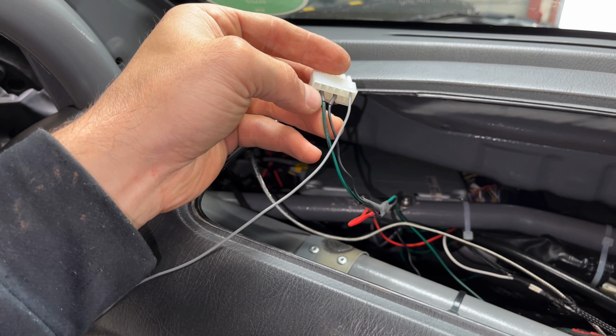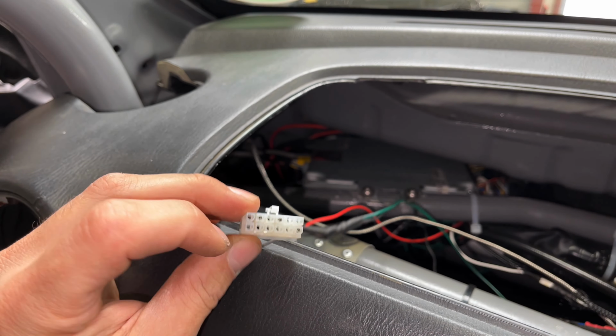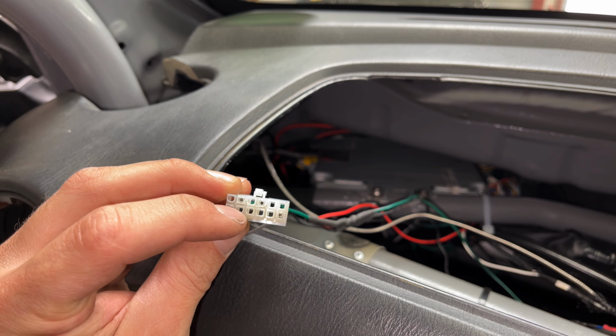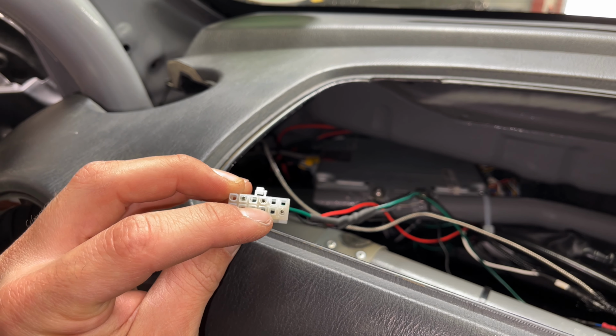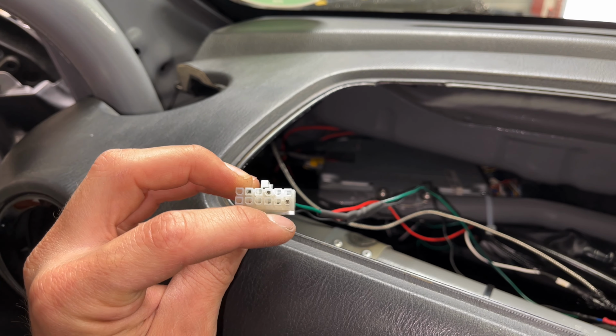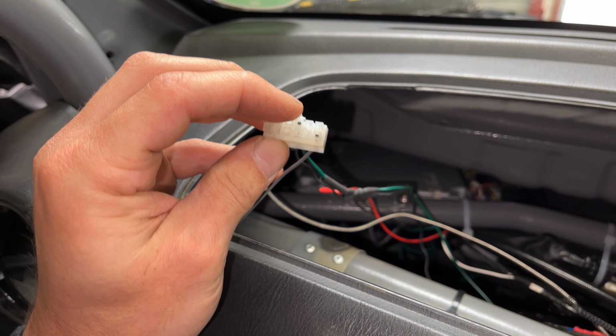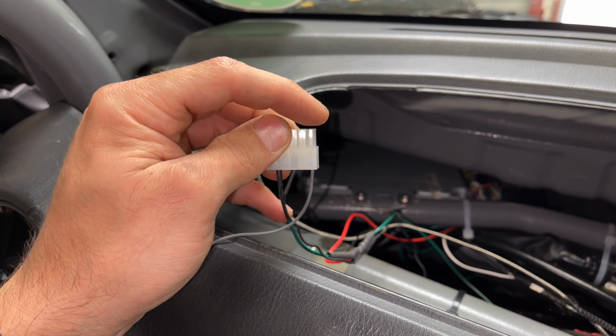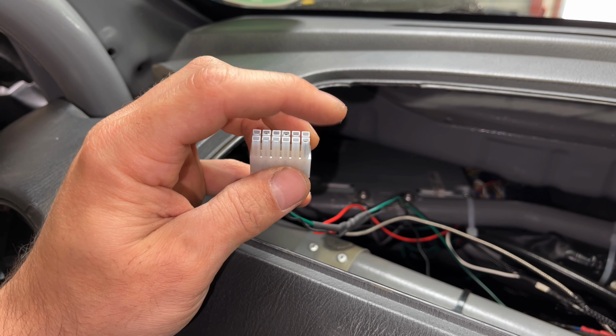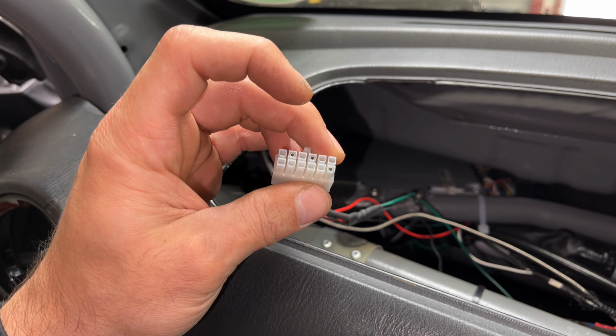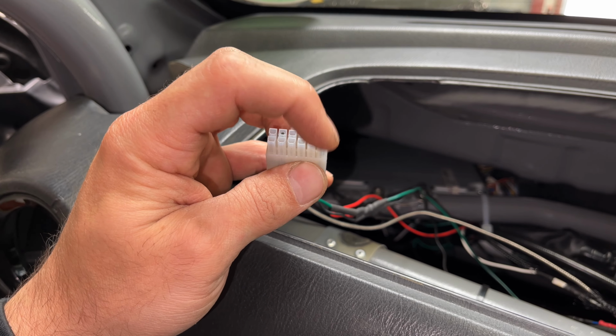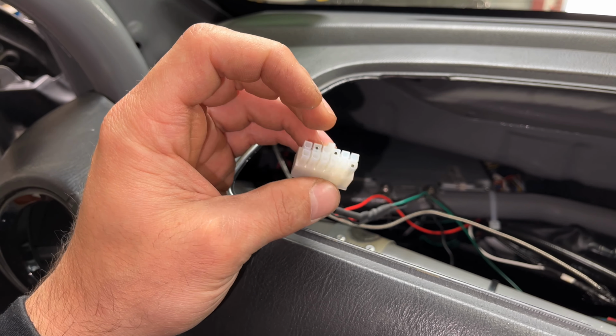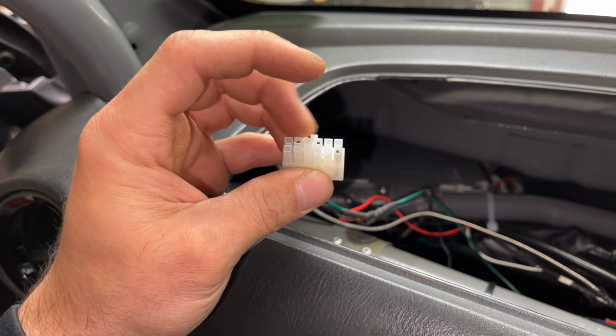At the minute, it goes that way - pins 1 on the bottom left, 2, 3, 4, 5. Pin 6 is the one we've gone into for IGN6, which was one of the spare outputs. Just remember, you can't have a high current output to this - if you were switching something like a fan, you'd have to go to a relay, a solid state relay or a normal relay. You can't go switching high current stuff directly.